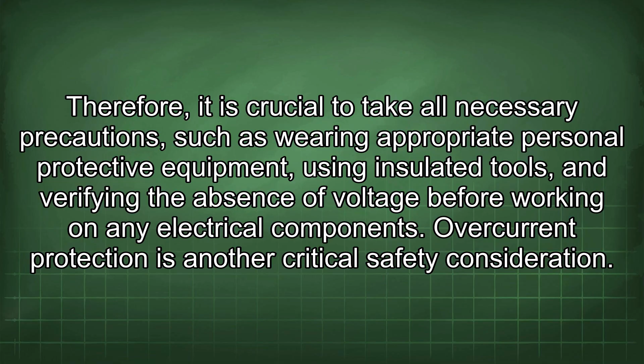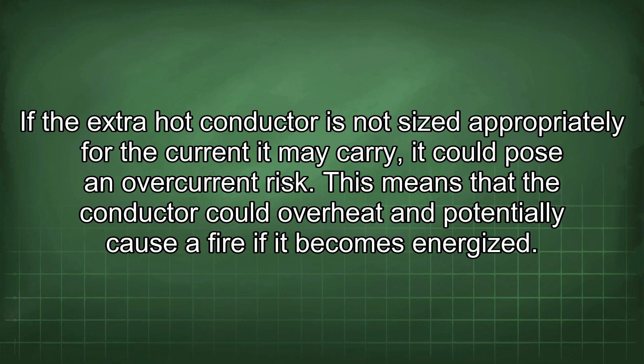Overcurrent protection is another critical safety consideration. If the extra hot conductor is not sized appropriately for the current it may carry, it could pose an overcurrent risk. This means the conductor could overheat and potentially cause a fire if it becomes energized. To prevent this, it is essential to ensure that all conductors are properly sized and protected by circuit breakers or fuses that are rated for the appropriate current.